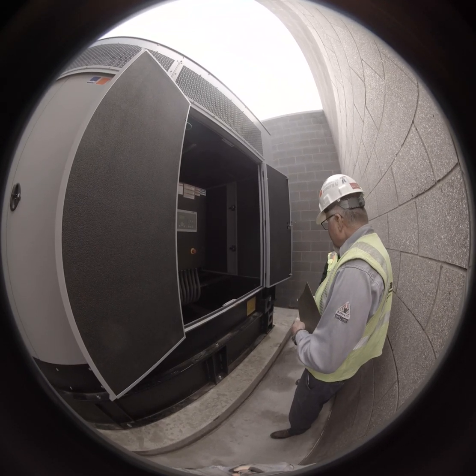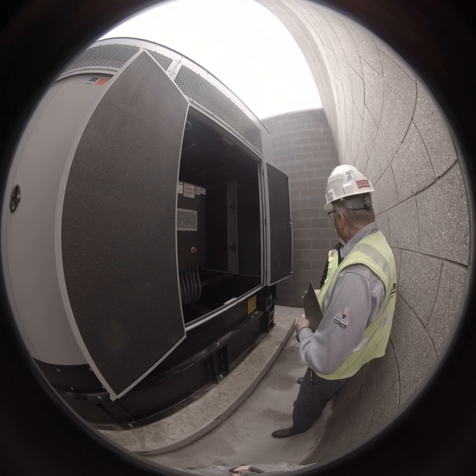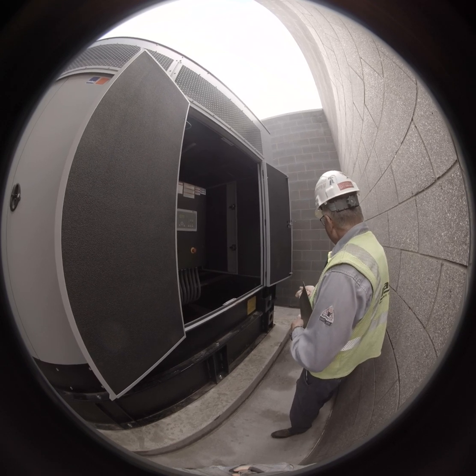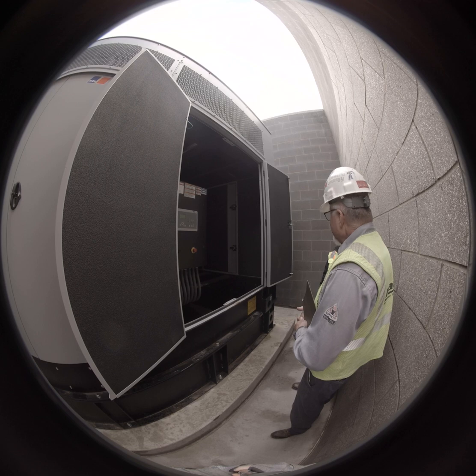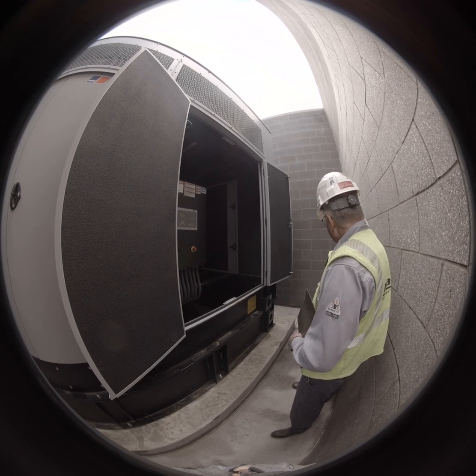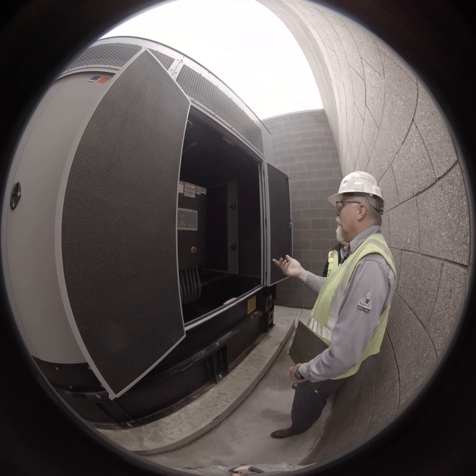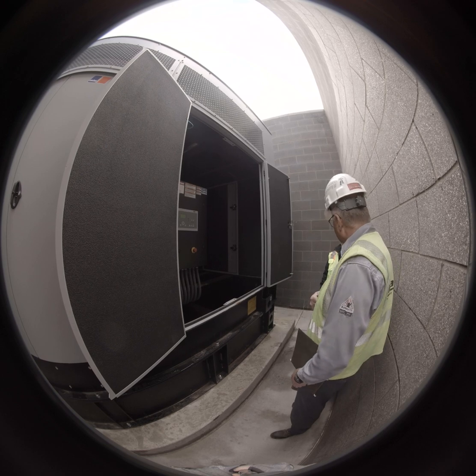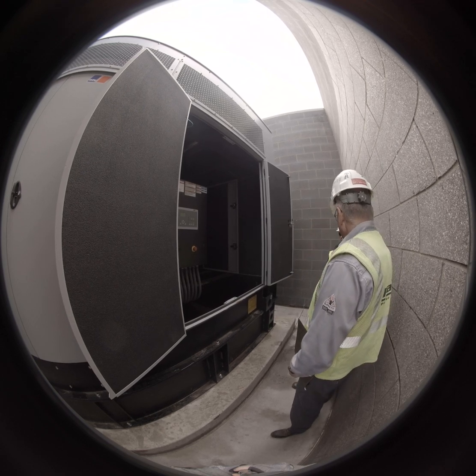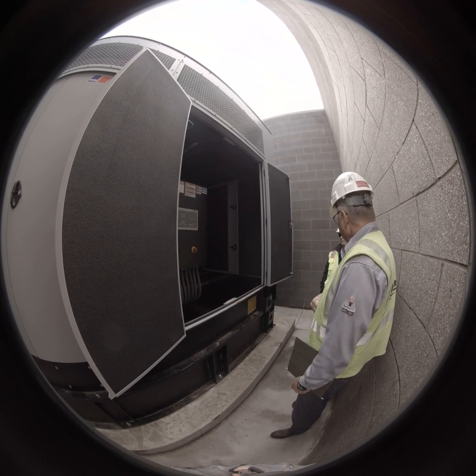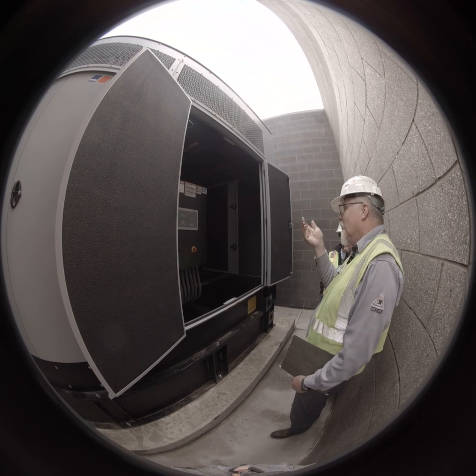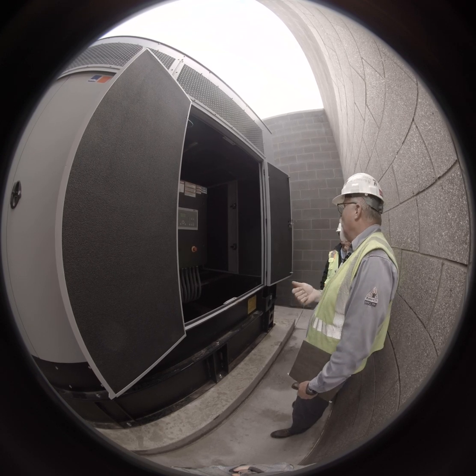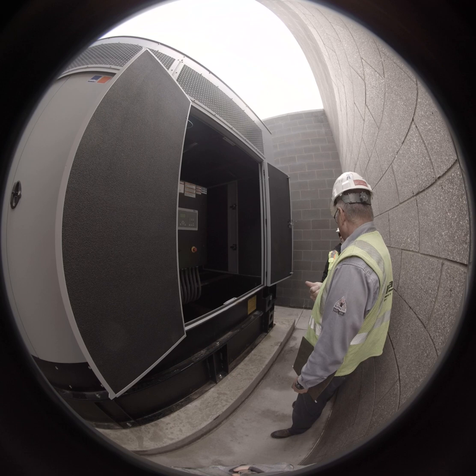So to back up my most recent statement of not getting in there and punching in the code, you can't do anything. Settings is something that I will put in there. You could go in and say, okay, I want my low fuel level to be at 25%. You could change that set point. It's all in there. But you need code. So for the majority portion of it, you will be going into the metering portion.